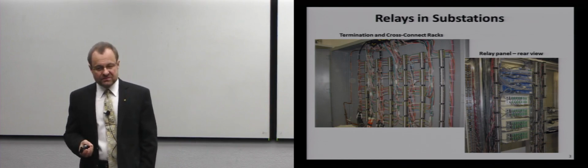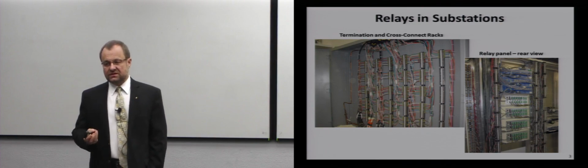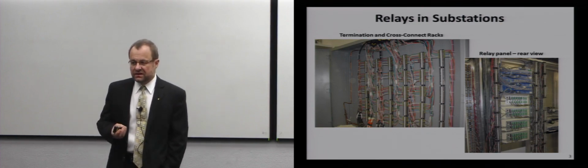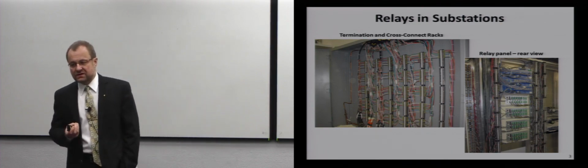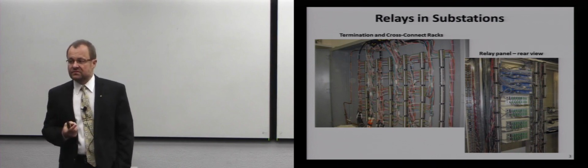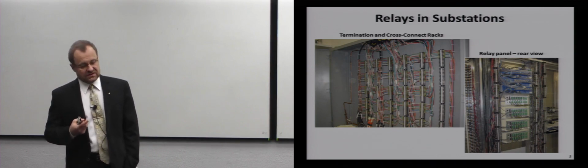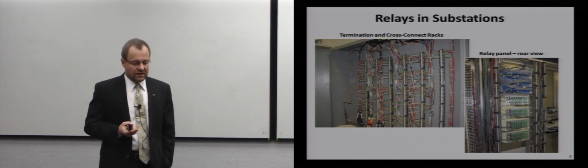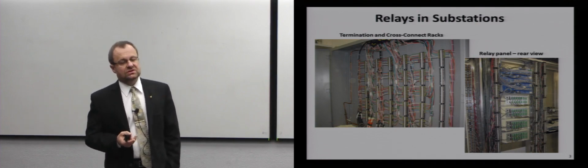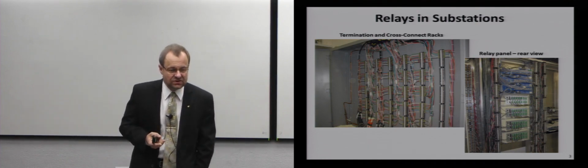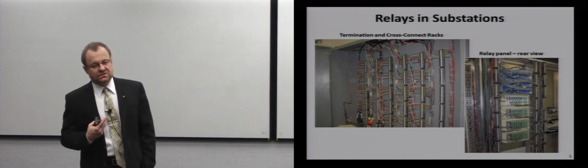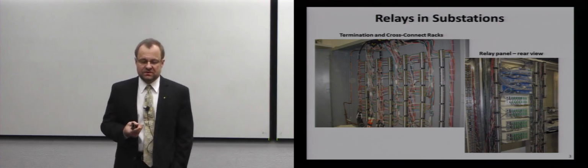We have a three-phase power system, so we have 3 signals per connection. Then to bring a signal back electrically, we need 2 wires for each signal. And then the substation could be big, so it's not uncommon in a big substation to have 500,000 terminations. When you bring those wires into a control house, you have to organize it, you have to label it.